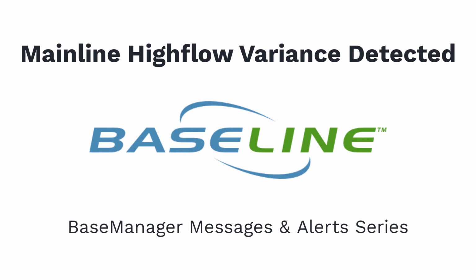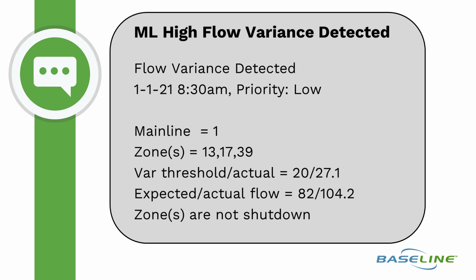Mainline high flow variance detected. The message reads, Mainline high flow variance detected, January 1st, 2021 at 8:30 a.m. Priority low. Mainline equals 1. Zones equal 13, 17, 39. Variance threshold versus actual equals 20 versus 27.1.